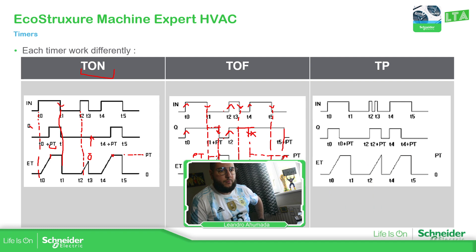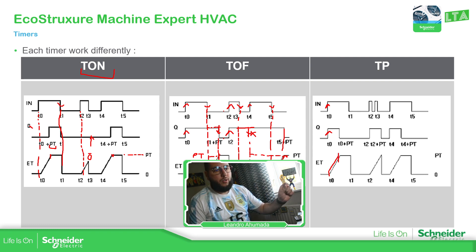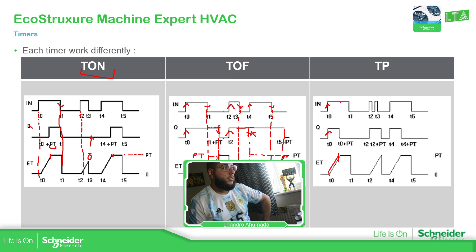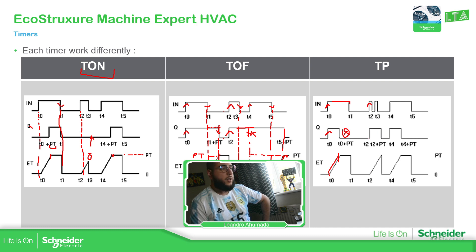Now the T-P — as soon as I activate the input, the output will be on for the duration I have already defined. This is the pulse. As soon as the input is activated, it sends a pulse of the specified duration. Even if the input stays true, it doesn't activate anything beyond that — it just stays on for the time specified in PT. It's not sending two pulses; it just sends one. That's the important thing.